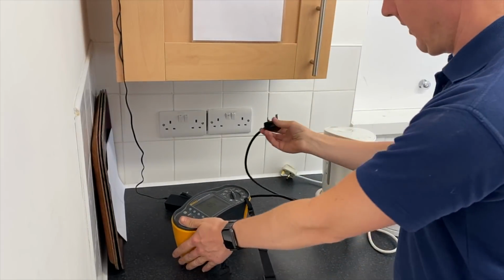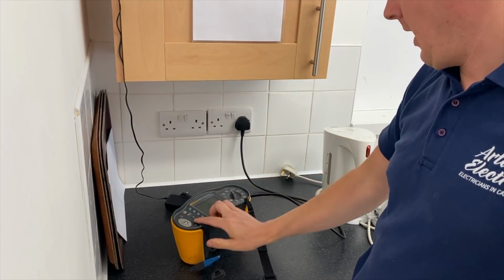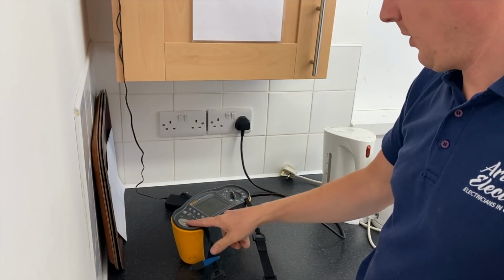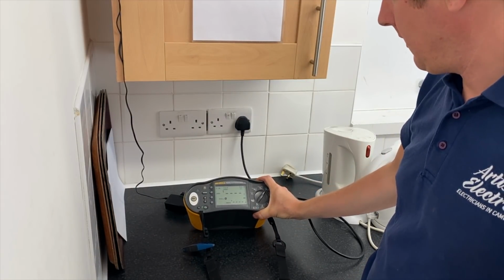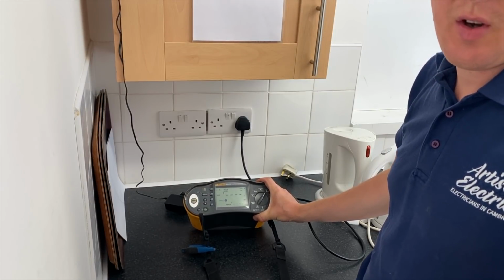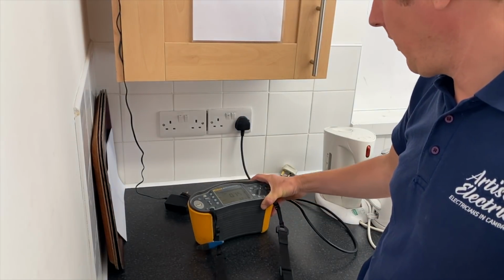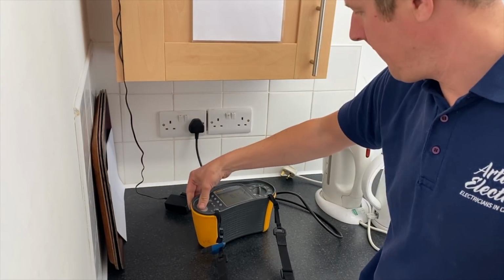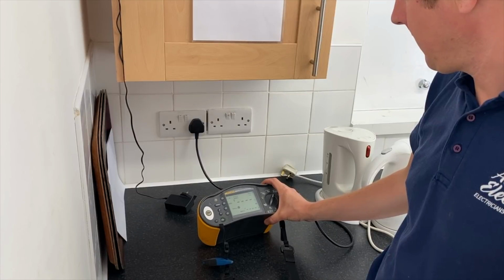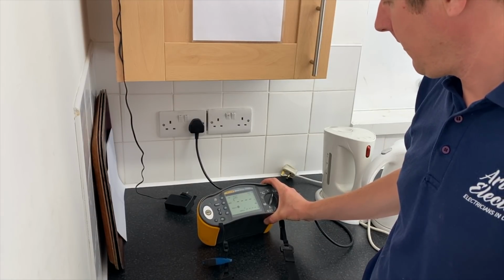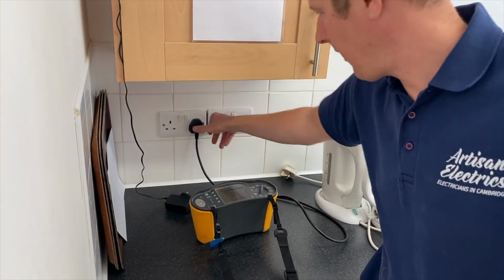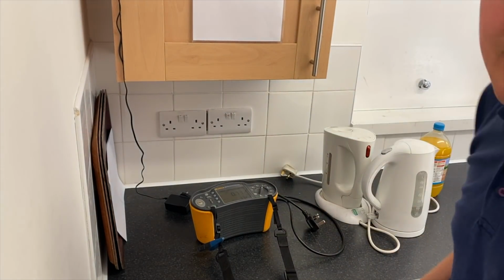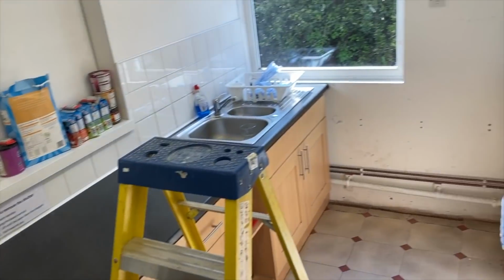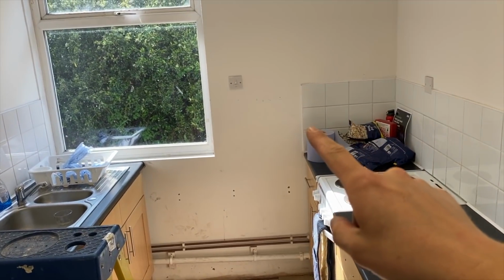So next we're going to be testing the socket outlets here in the kitchen, and they're really easy to test because all we do is plug in and then do our test reading. I usually like to test all of the sockets just to make sure that the polarity is correct on all of them. So we've got 0.75 there. 0.73. There's one under here, so I'll test that, and then over there is a switch fuse connection unit which is for the fan, so I'll test that one as well.